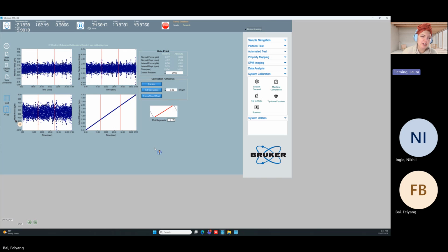How we judge the calibration is based off of the lateral force. What we typically like to see is that it's centered around 0 and the spread is roughly 10 micronewtons or below. It looks like that's mostly true here. We're offset a little bit. That's pretty typical when the transducer first goes into scratch mode. You're turning on a bunch of circuit boards.